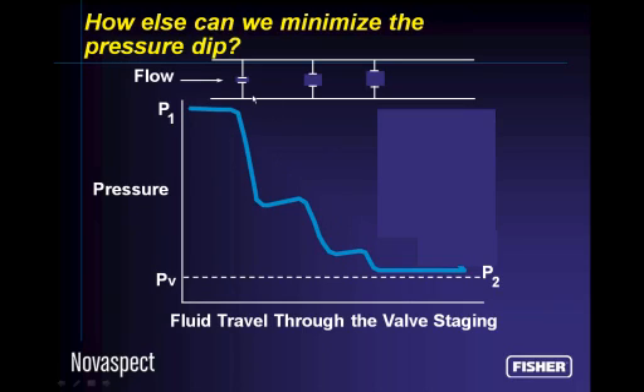What if I decided to put 3 valves in series and take a little pressure drop across each one? Well, first of all, it would become obvious that each successive valve would have to become bigger and bigger, because we have less pressure drop available across each one to get the same amount of flow through it. But I could take this first valve and take a pressure loss and then provide some room for recovery. Then through the next valve or orifice, take another pressure drop and then take a little recovery and then take another one.